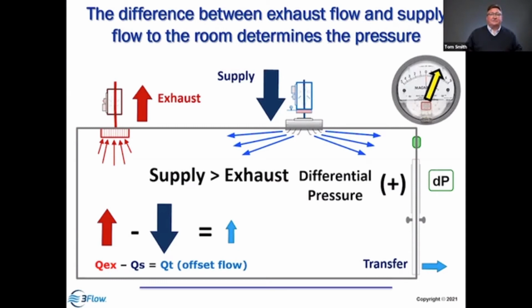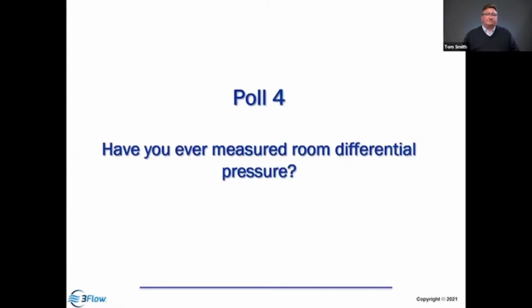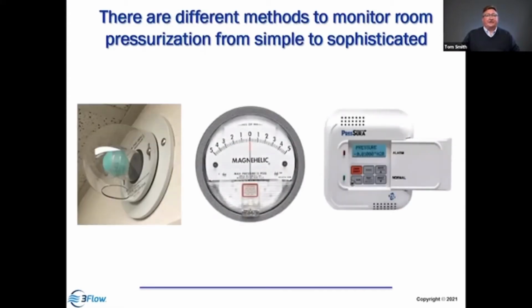So the pressurization of the space, and this concept of the volumetric transfer air, the offset transfer, is the difference between supply and exhaust, and it must be appropriate in order for the hood to function properly as well. So this is often overlooked when we're evaluating the air balance for spaces. Okay, so this was the question: have you ever measured room differential pressure? Quite a few people had, but quite a few people didn't. And so we're going to talk about how to do this measurement and what the appropriate technique is. In addition, we need to look at what types of monitors are available. I think that every room should have a monitor to indicate this pressurization, and there are different types.